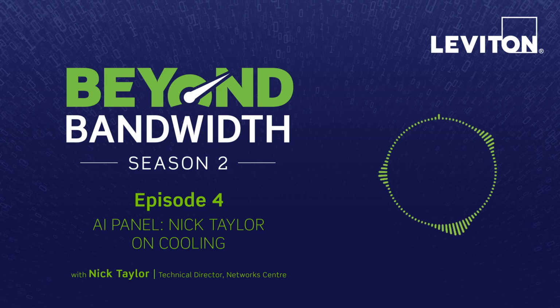And then obviously with immersion liquid cooling, instead of blowing cold air, you submerge the entire system into a dielectric liquid. I'm still quite amazed by this when I see it, seeing servers dropped into this liquid. It doesn't conduct electricity, obviously, otherwise it wouldn't work. But it does cause all sorts of other issues. Like, for example, if you want to use normal patch cords, the sheath will not survive. Most of the sheaths that we're using these days are PVC or low smoke zero halogen along those sort of lines. Neither of those are good enough.